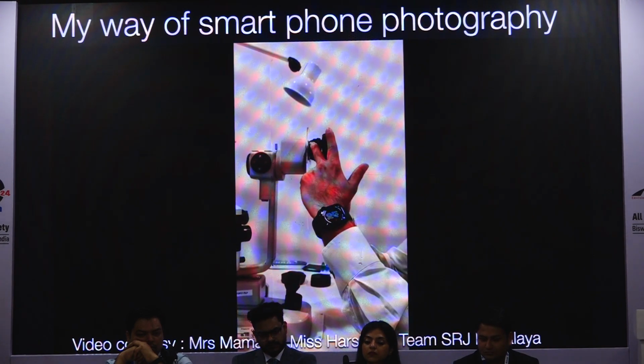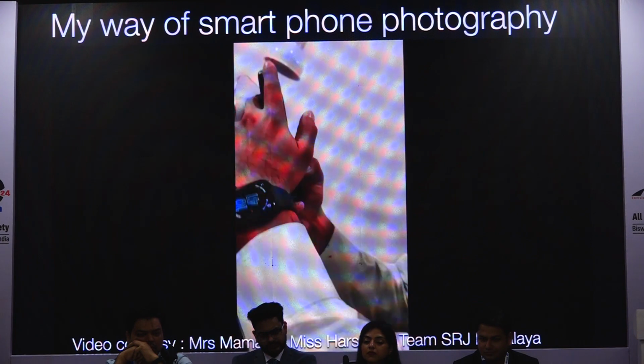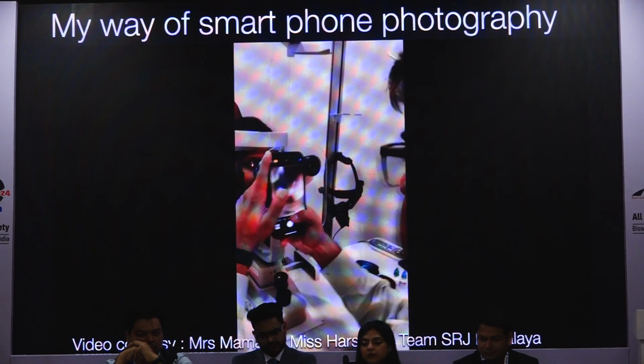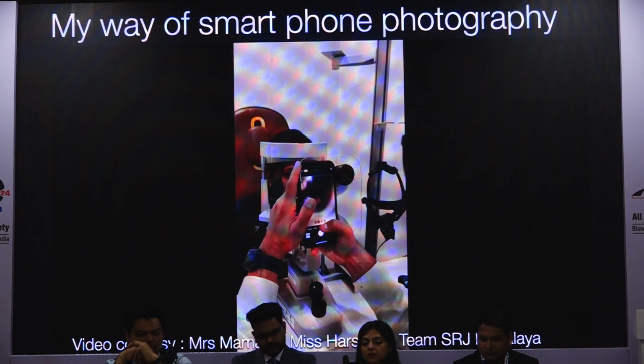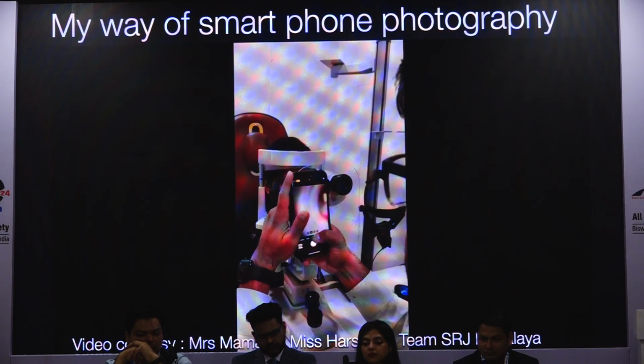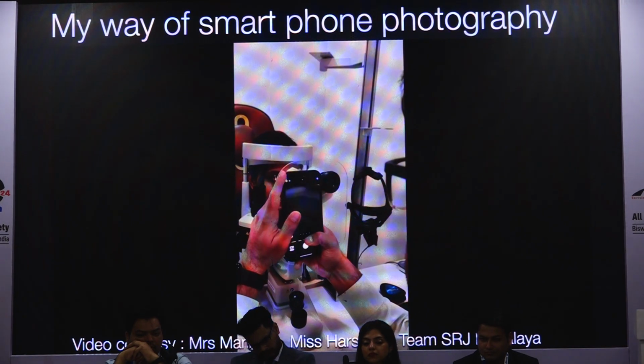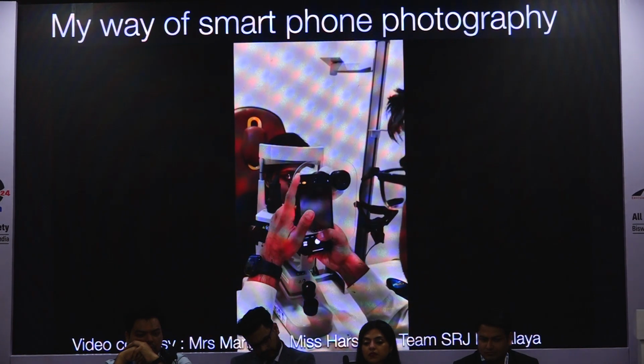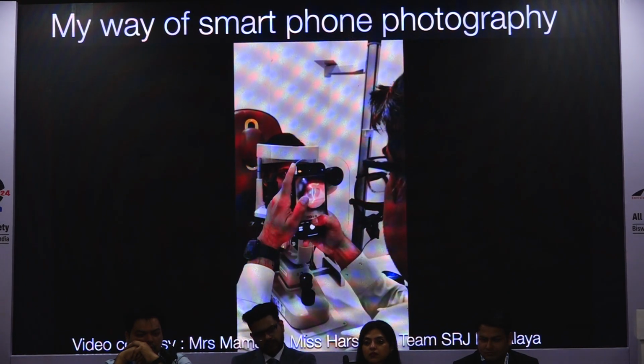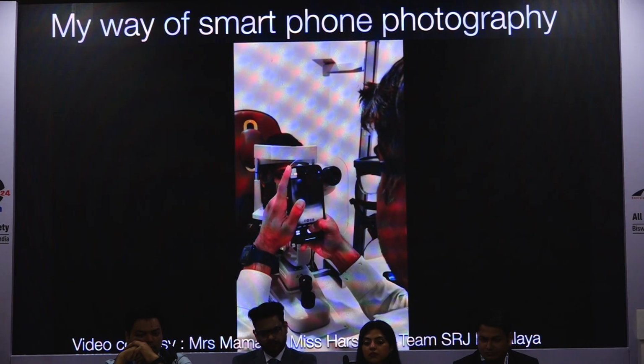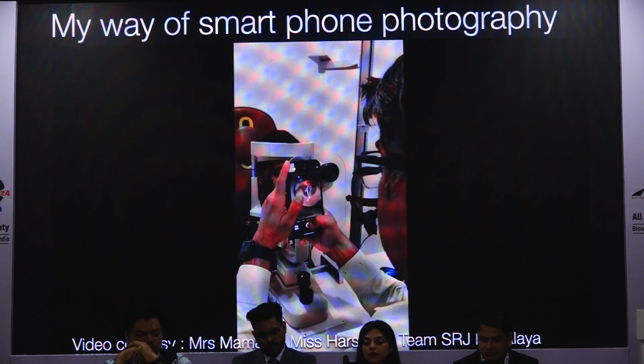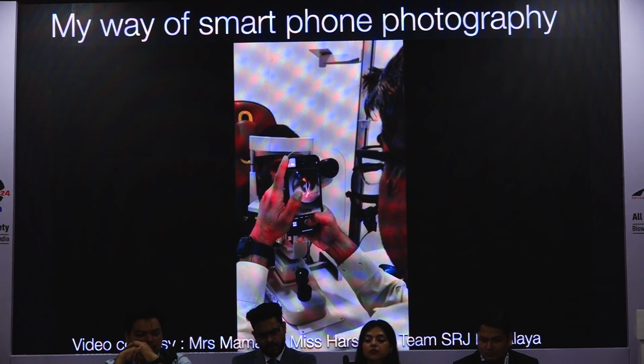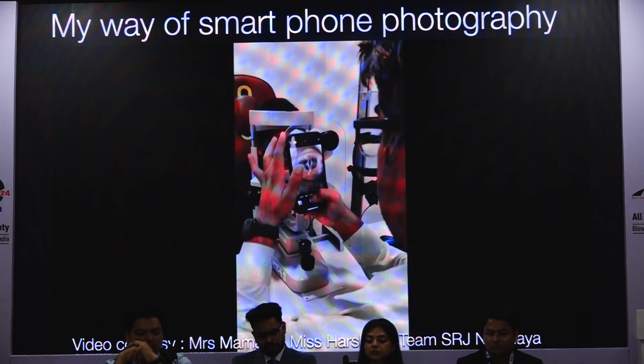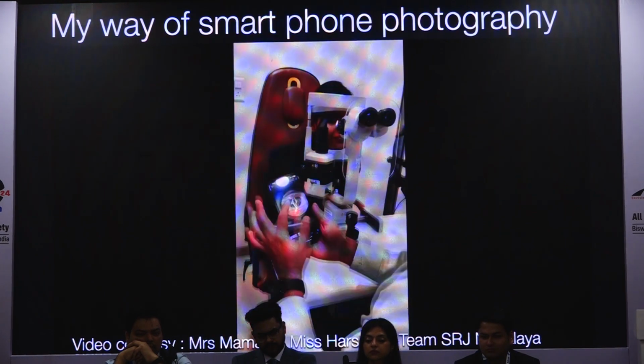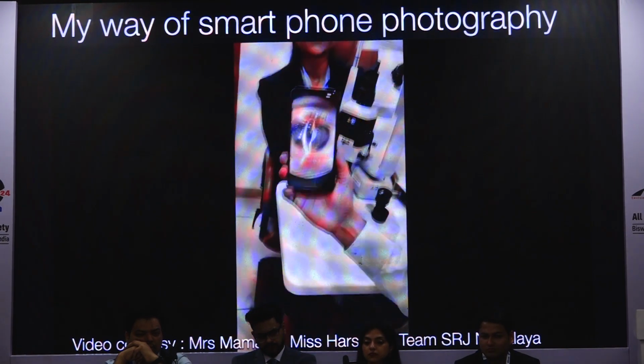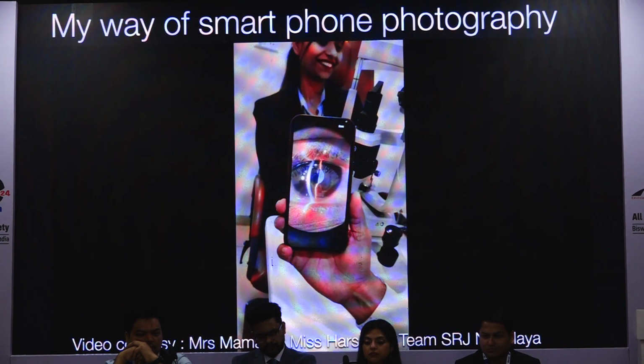and I'm moving my phone with the camera right and left, and you just wait until the image is formed. You know where the image is, and you need to be ready with your other hand on the click area with the thumb. Once you get an image, you need to hold the phone in the correct position, and you just click a picture, and that's it. The advantage with the smartphone is you don't need to worry about other parts like illumination. So you can see the image, which is quite clear, and it is actually a slit image.